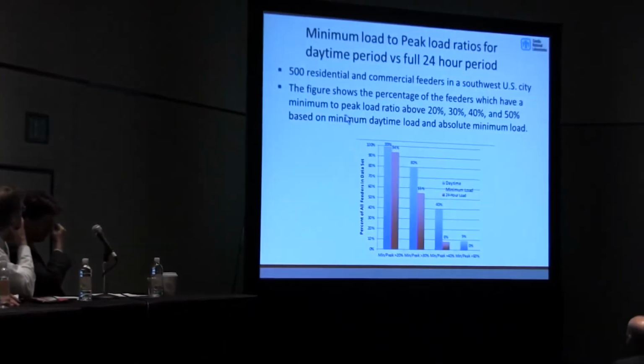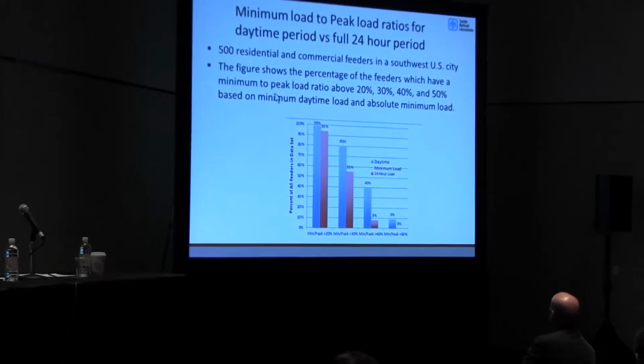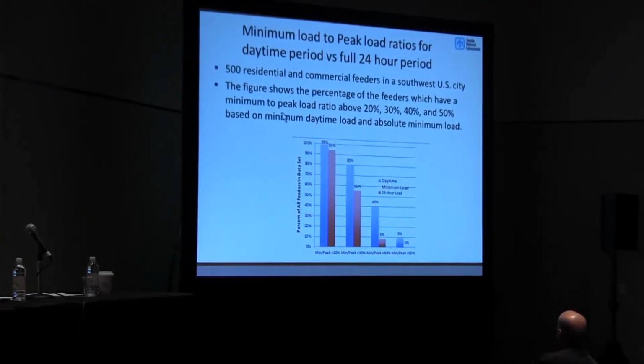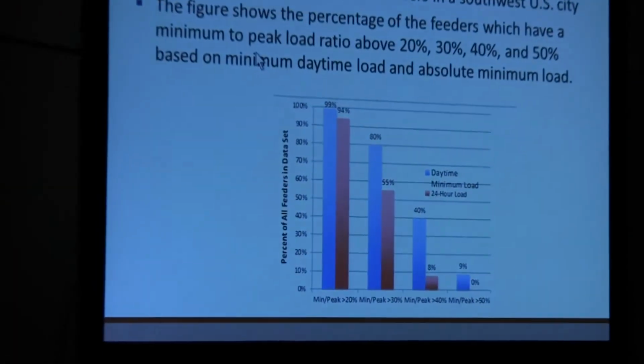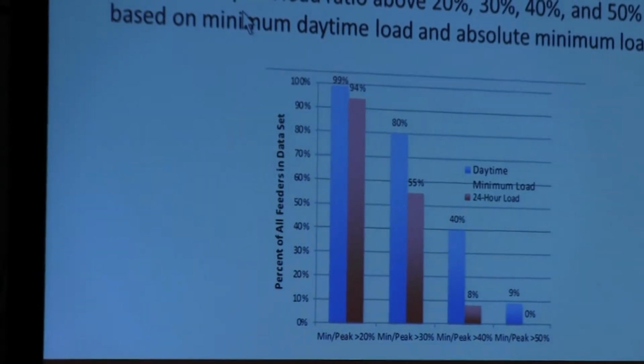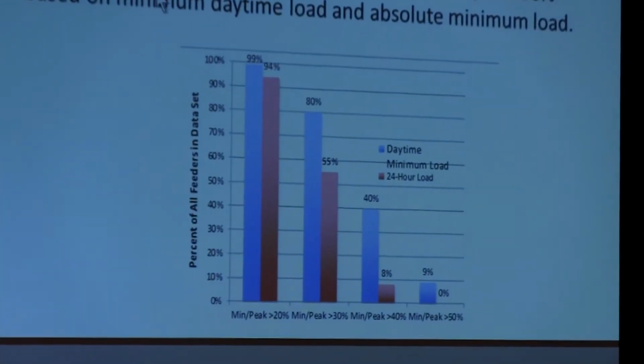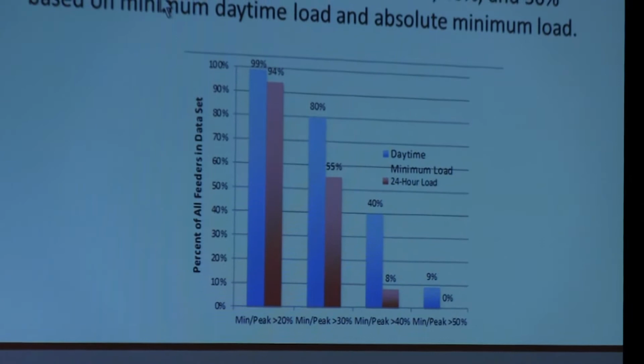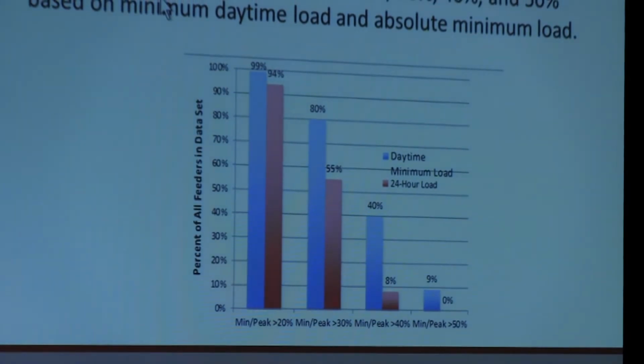And what this data shows is the comparison between looking at minimum load data only based on the 24-hour, that's the red that you're looking at, or looking at it based on daytime minimum load. The main takeaway is to look at the two columns to the left. Over 80% of the feeders are greater than 30% peak to min load ratio if you use daytime. If you use the 24-hour, you're only at 55%. So this, of course, raises the question, what is the best way to establish the threshold?